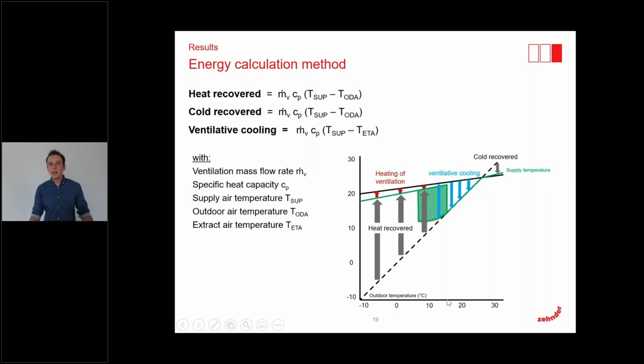Before we come to the energy savings, I just want to explain shortly how the energy savings were calculated. This is done by the best-known formula of building engineering. For the heat recovery, we have the mass flow of the air times the specific heat capacity times the temperature difference between supply and outdoor air. The same applies for the cold recovery. For ventilative cooling, we are taking the supply and the extract air into consideration because we do not use the heat recovery.